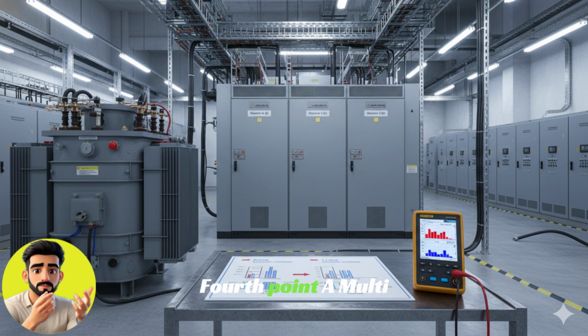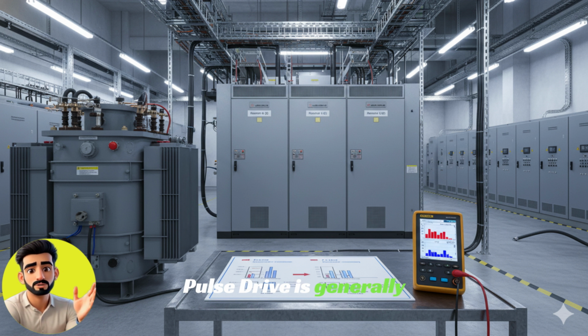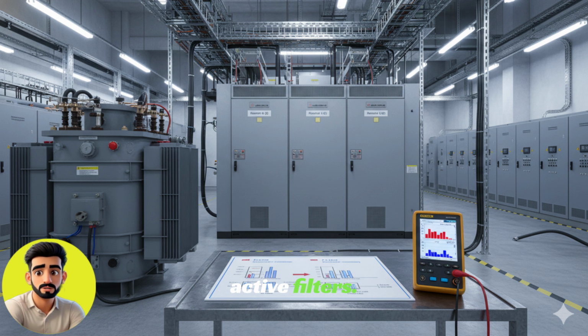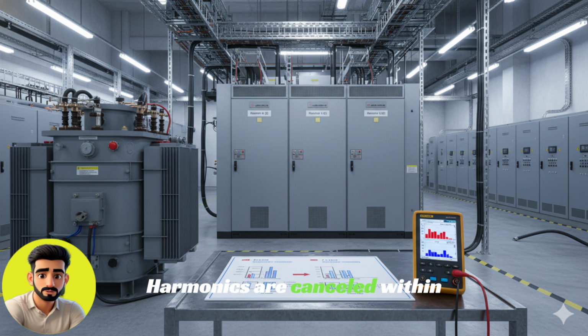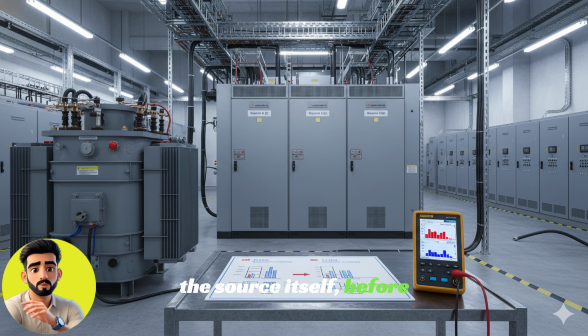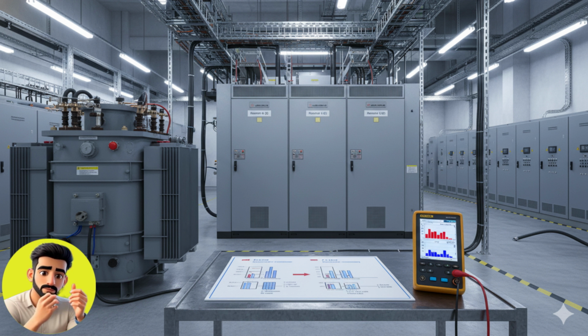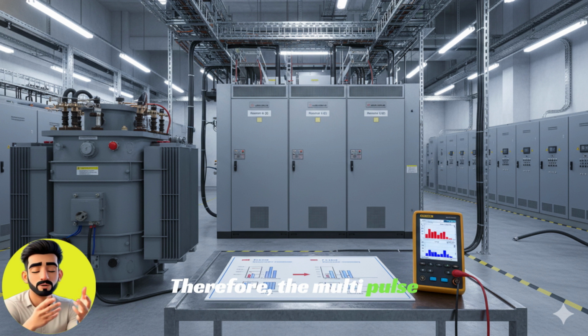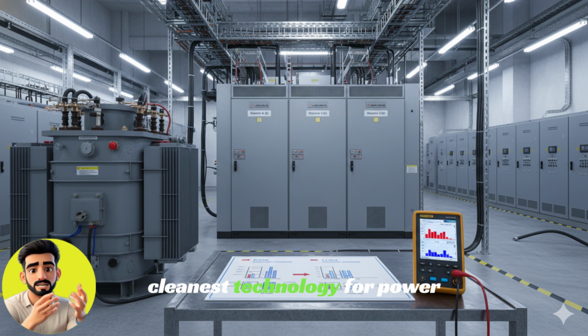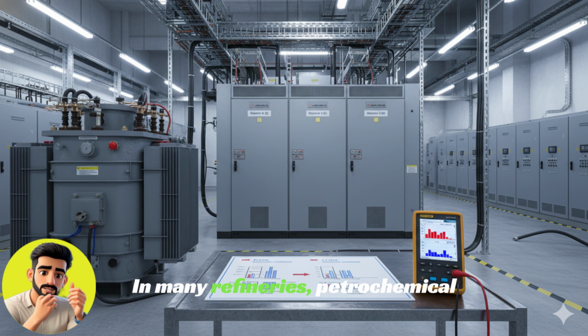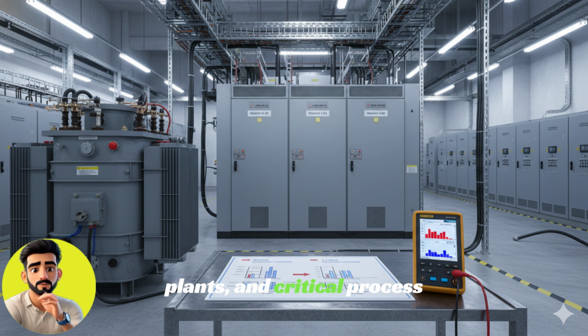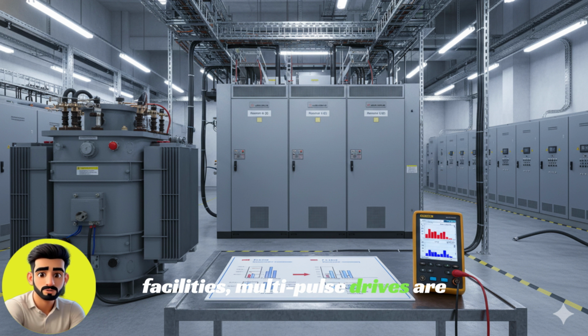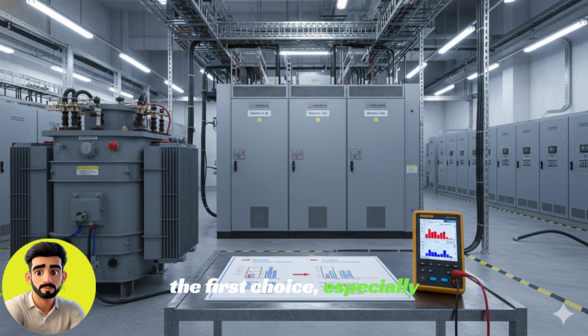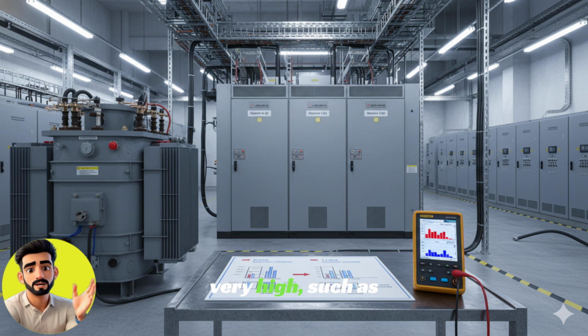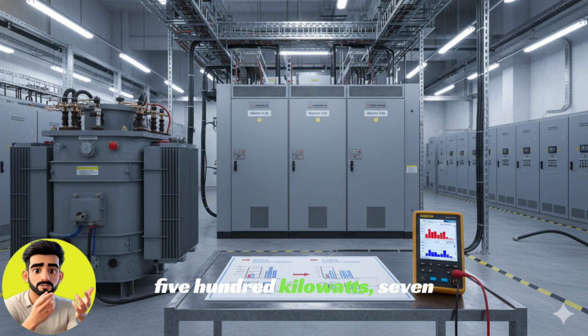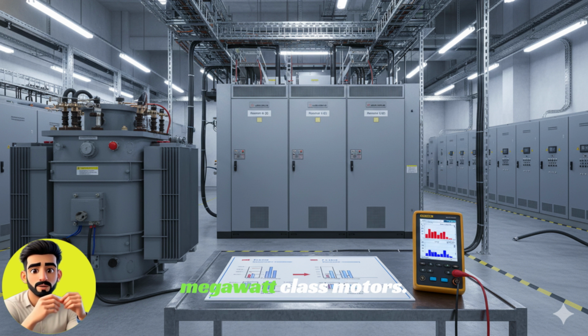Fourth point. A multi-pulse drive is generally better than passive or active filters. Harmonics are cancelled within the source itself before any distortion enters the system. Therefore, the multi-pulse drive is considered the cleanest technology for power quality. In many refineries, petrochemical plants, and critical process facilities, multi-pulse drives are the first choice, especially where drive ratings are very high, such as 500 kilowatts, 700 kilowatts, or 1 megawatt class motors.